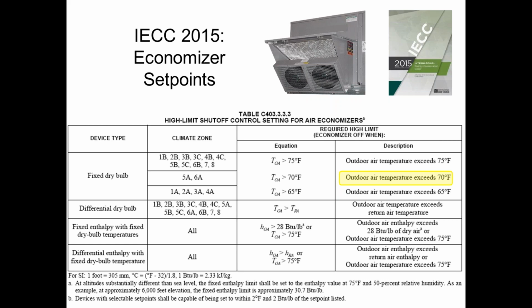Previously, some of you guys probably still use the old 55 number because someone told you to use that 25 years ago, the first day you went on a job. So now if it's 69 degrees outside, I'm in an economizer day, and I've got to open up my economizer for free cooling. Now I know you're thinking, I can't really cool your building at 69 degrees, right? So that's true. I'm going to have to run compression with the economizer in most of those cases, which we'll talk about in a little bit. But you no longer set the economizer for 55 or 60. You now set it for 70 degree outdoor air temperature. If you're doing enthalpy, you'll set it for 28 BTUs per pound of dry air. And you can also have, in addition to that, a 75 degree maximum cutoff temperature as well.